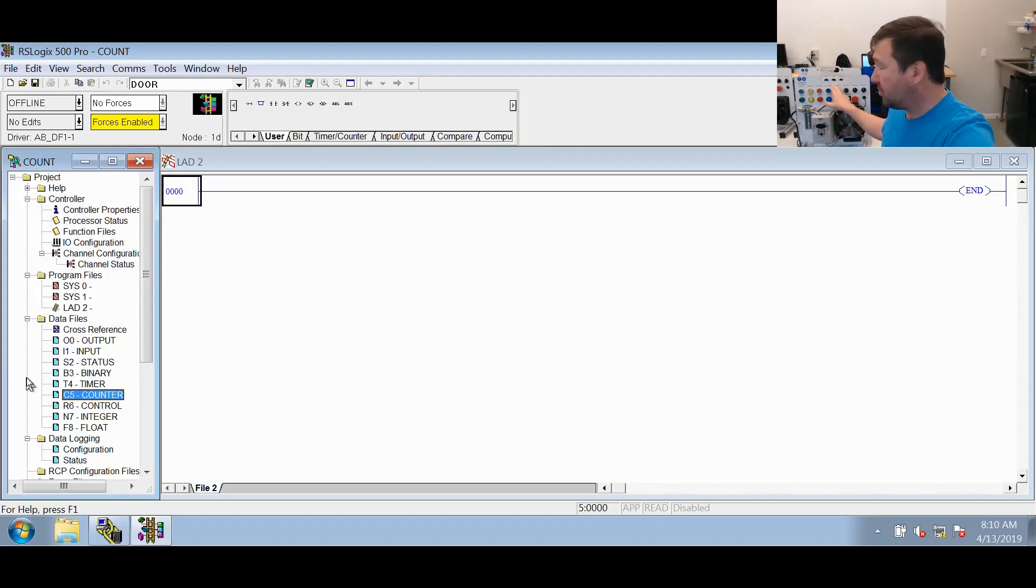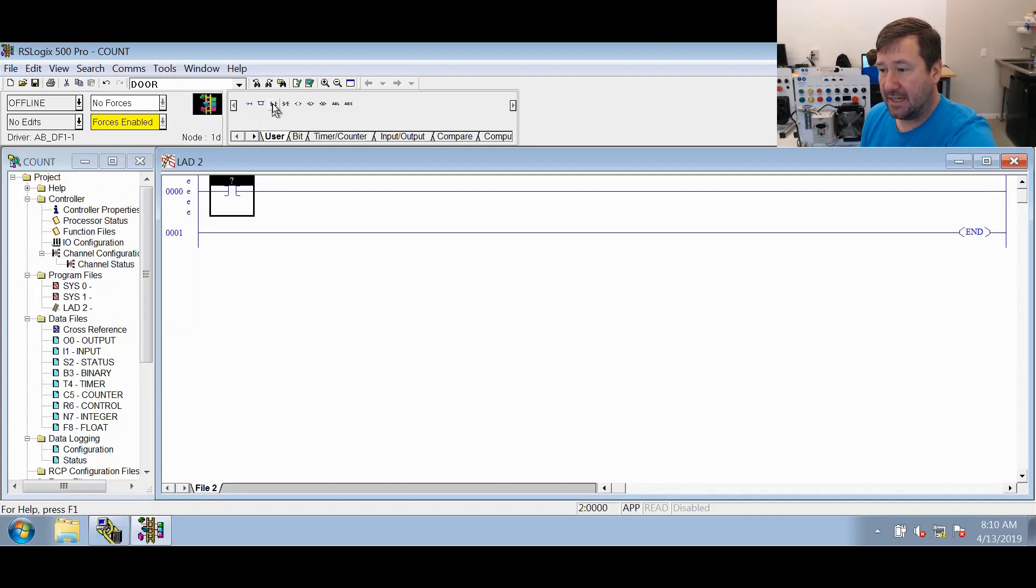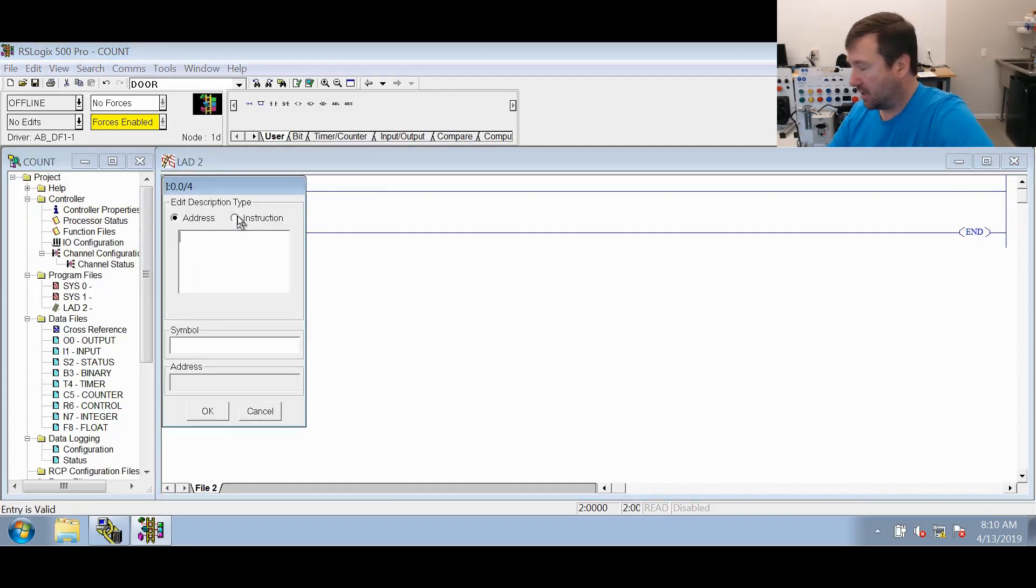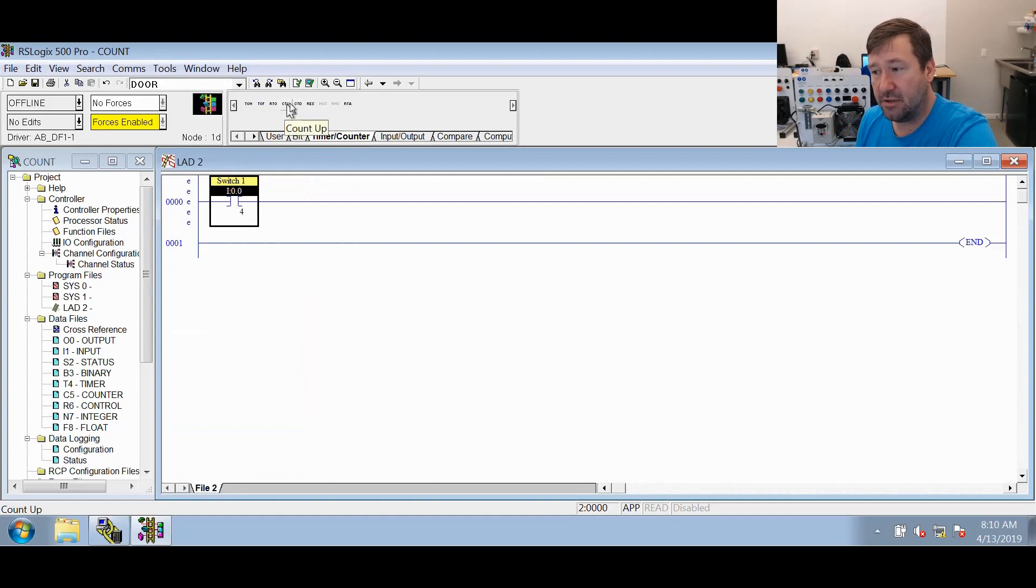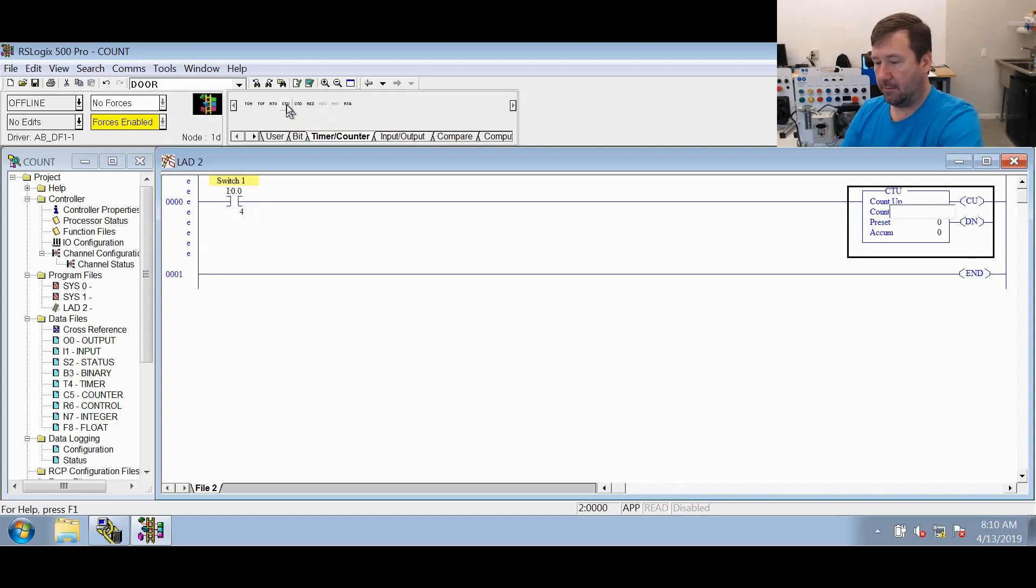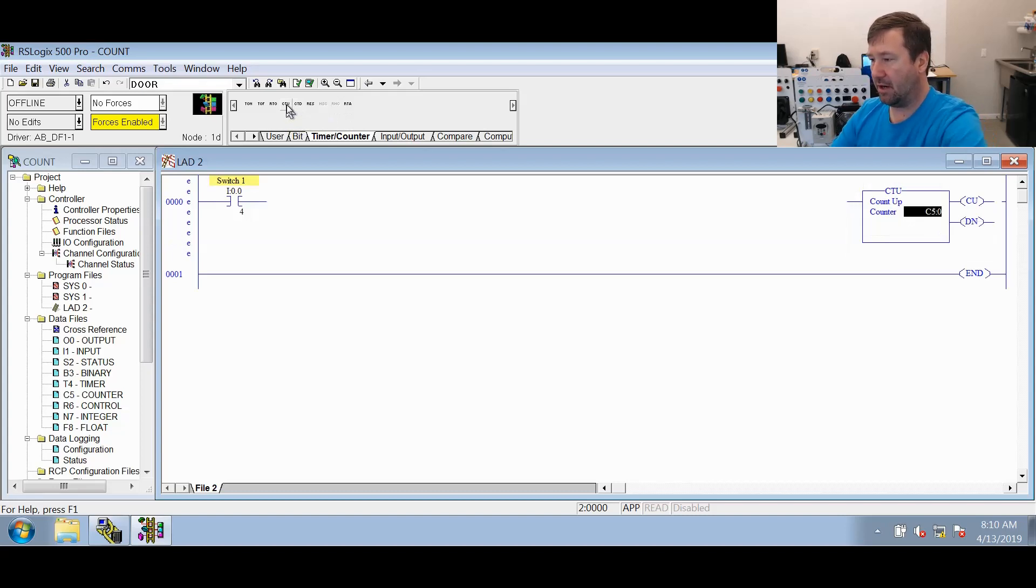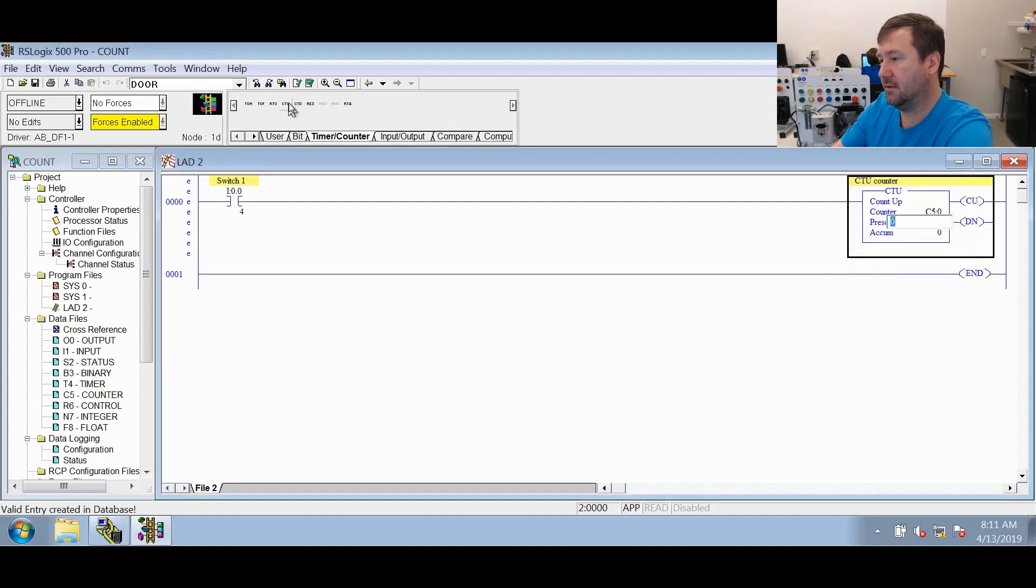So we're going to use switch one to control our counter. We're going to just put an XIC of I:0/4 because that is what switch one is connected to and we'll just call that switch one. Then we're going to go to our timer counter tab. You can see we have a CTU and a CTD instruction. So we're going to select the CTU instruction and we'll assign it C5:0 and we'll just call this our CTU counter. And let's put a preset of 10.